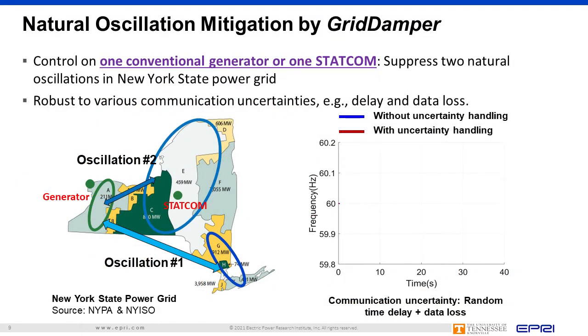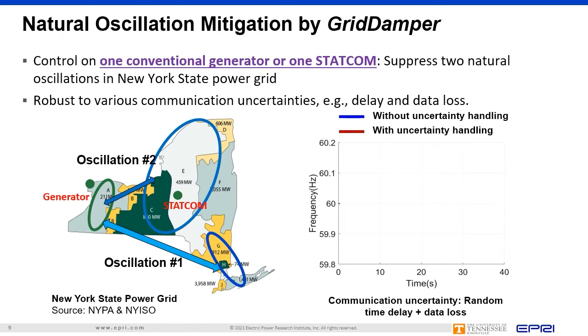Another application of Grid Damper to natural oscillations is in the New York State Power Grid. Grid Damper detected two natural oscillations — the west against the north, and the west against the south. The oscillations were quickly suppressed through Grid Damper's action on a voltage compensator, and control can also be executed through conventional generators.